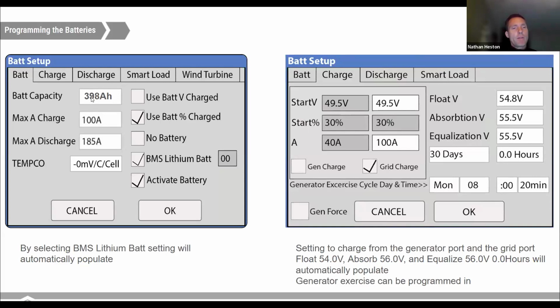These are settings for a whole home battery backup system. So your max overall charge and max overall discharge are in amps DC. Under the battery tab, you have a max charge and a max discharge rate. These are global limits, and what I mean by global limits is they incorporate solar charging at the same time as maybe grid charging. If I set my max charge rate at 100 amps, you might have 20 amps coming from solar and then 80 amps overall coming from the grid. So it will limit the combined charging to this value.